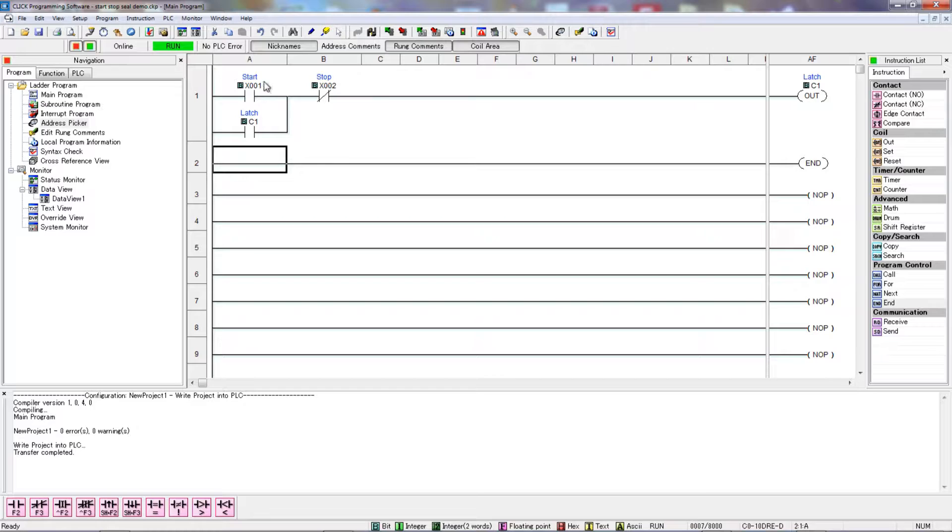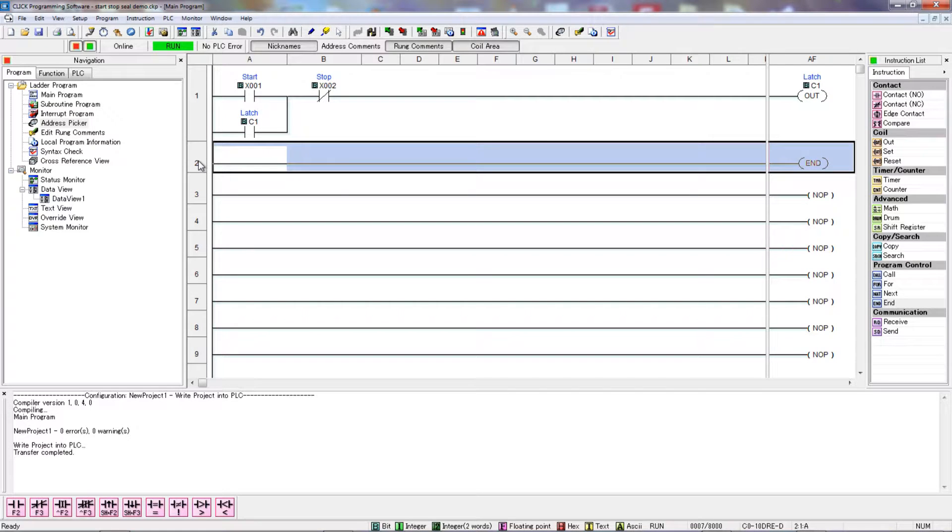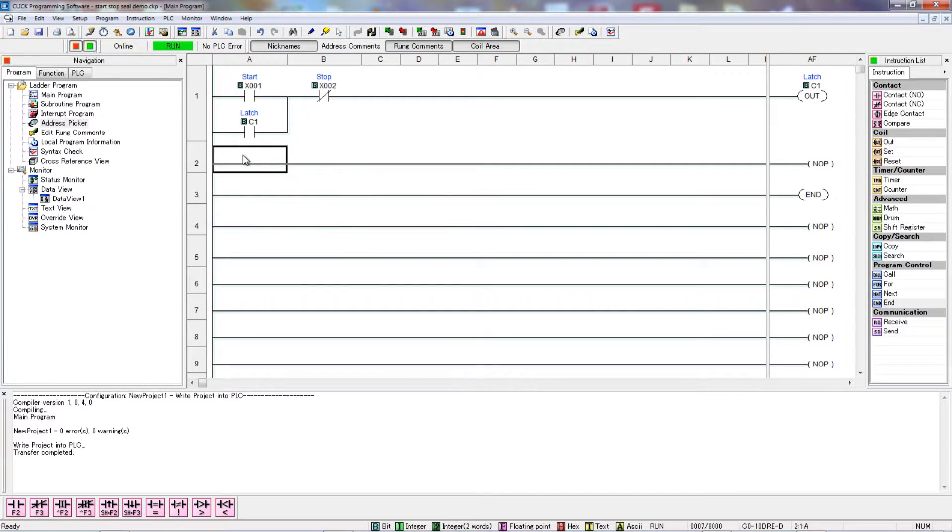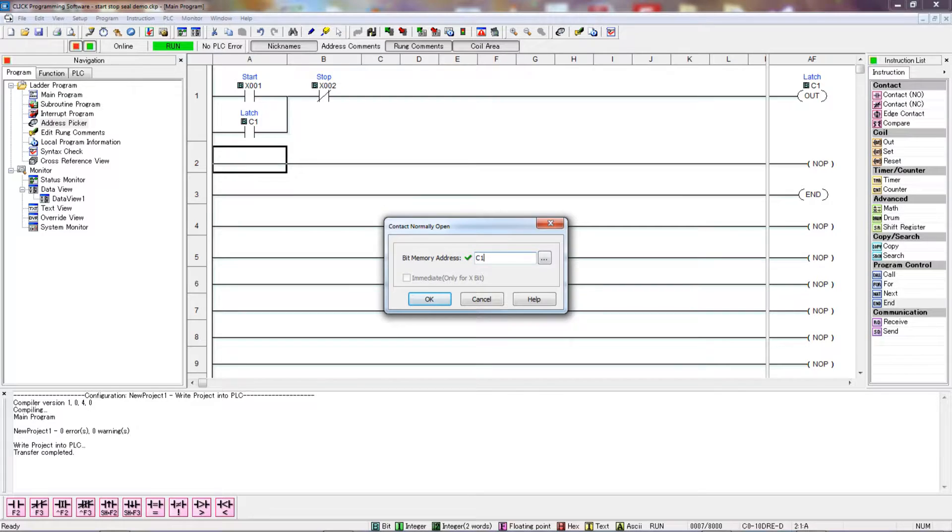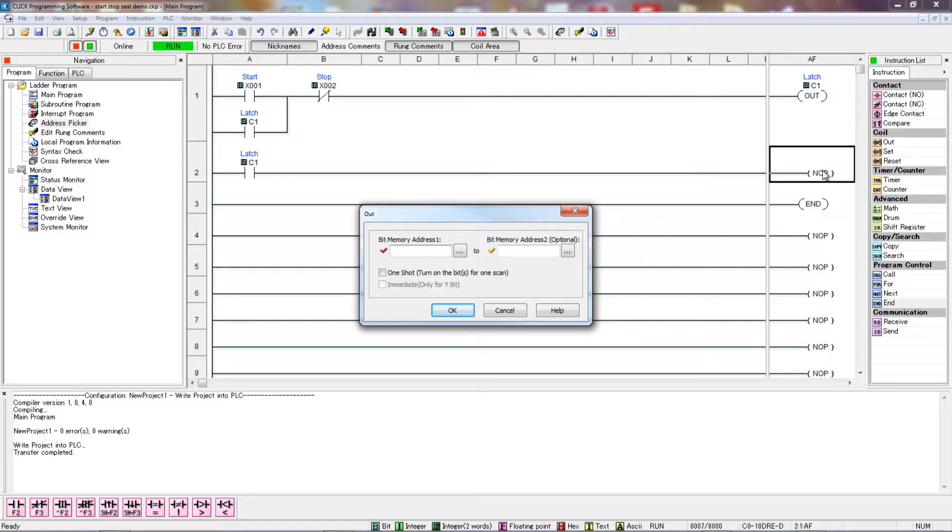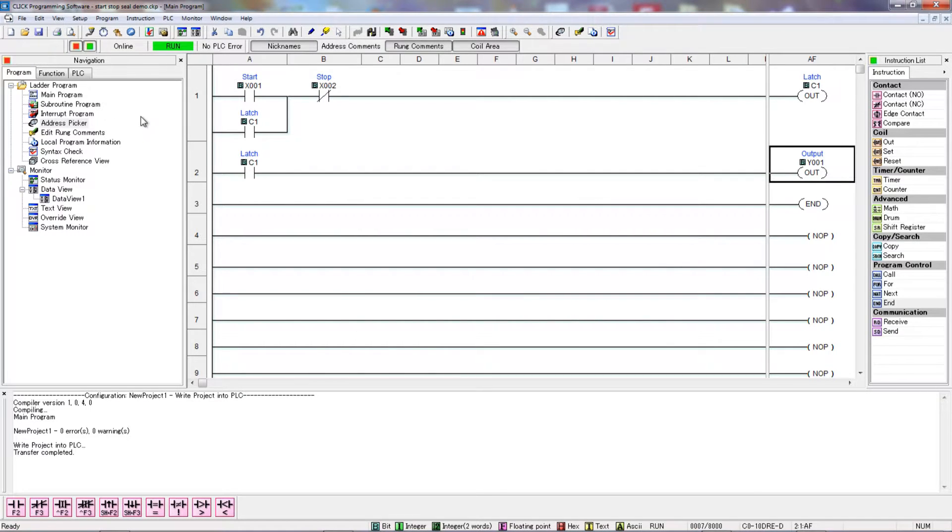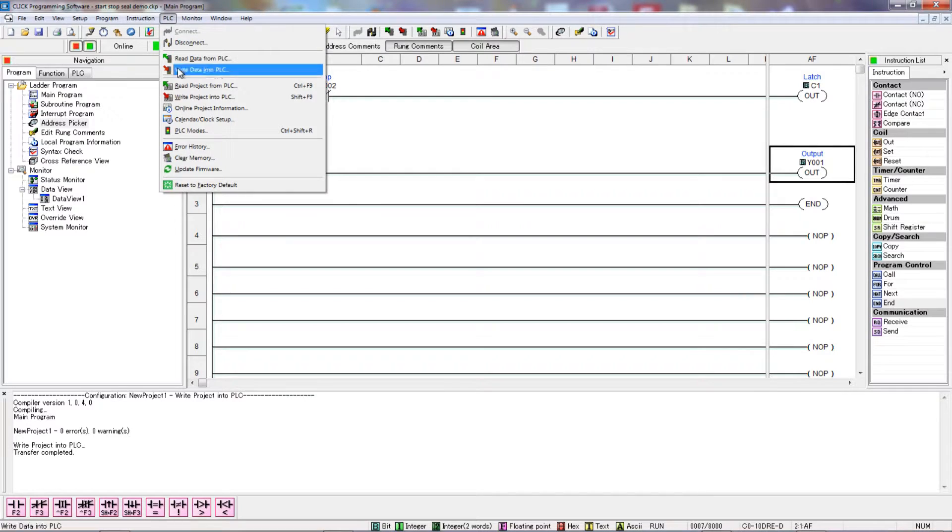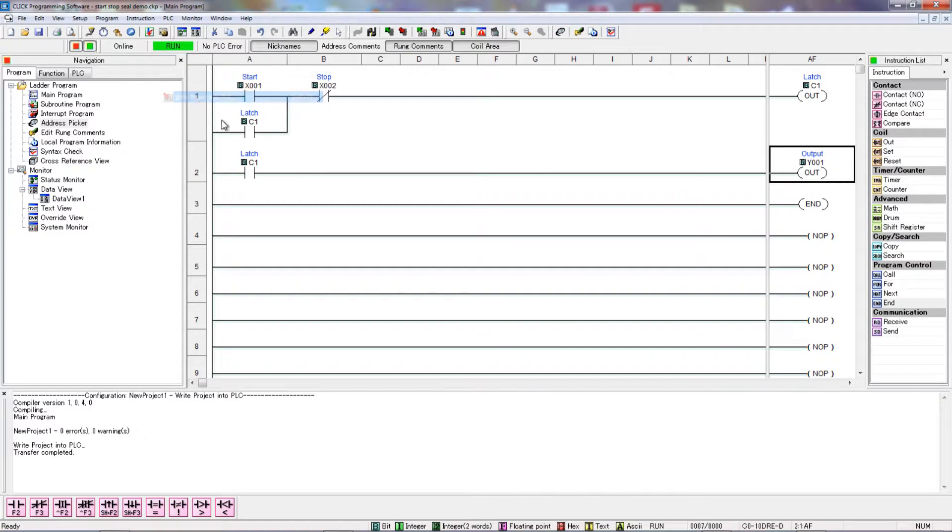Now, that doesn't do a heck of a lot right now because it would just latch this internal coil onto it. So, the next thing I want to do is I'm going to right-click on this, insert a rung before cursor, just so I can pop my end instruction down one. I'm going to hit F2 to insert C1. And I'm going to tie that to that real-world output we used before. I double-clicked on that. Y1. So, now this will latch on and turn on my output. And we're going to get to the timer in a bit, but you'll be able to see where I've essentially just offset this using an interposing internal relay. And we can download this into the PLC as well, just to make sure it works like we think it will.